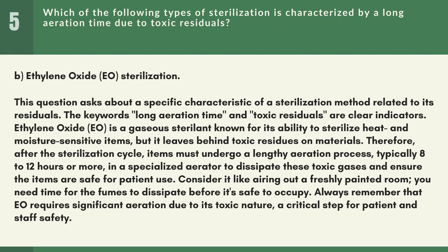Answer: B. Ethylene oxide, EO, sterilization. This question asks about a specific characteristic of a sterilization method related to its residuals. The keywords long aeration time and toxic residuals are clear indicators.